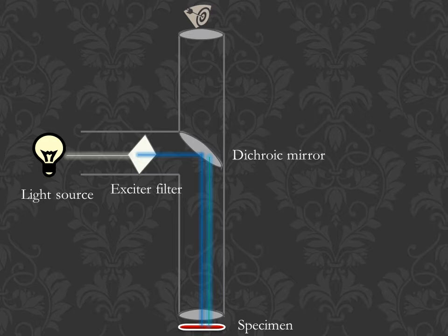Now when this reflected light passes through the dichroic mirror, only green color can pass through it, because blue color would definitely be reflected, as it is designed in this way, right? Green color, since it has longer wavelength, is going to pass through the dichroic mirror. That's why it has become a bit more green now, right? Though it is still not total green, we need a pure green spectrum of light. That's why we use another filter at this end, near the eyepiece.